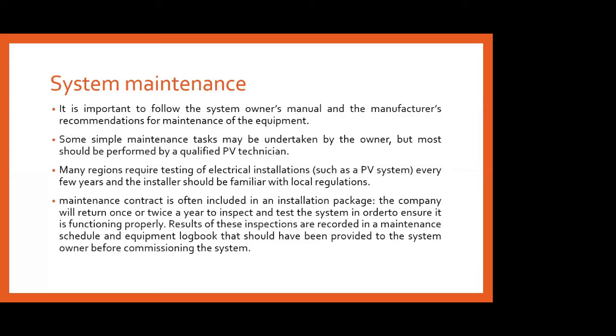Of course, the company will return once or twice a year to inspect and test whether all the equipment is functioning properly. The results of these inspections also have to be recorded and maintained in a maintenance schedule and in the equipment logbook. All those things will be provided before commissioning the system. In addition, maintenance contractors should keep a record of service and repair work, and a copy has to be maintained with the owner.